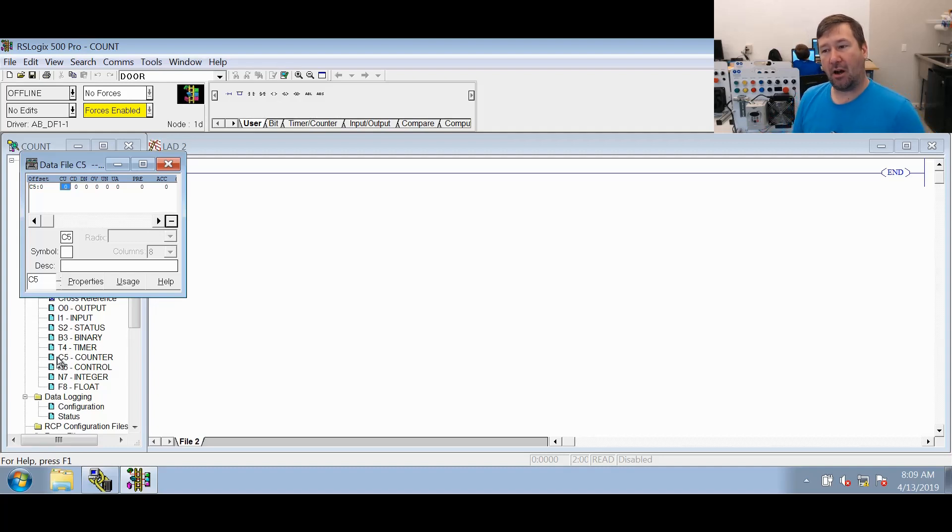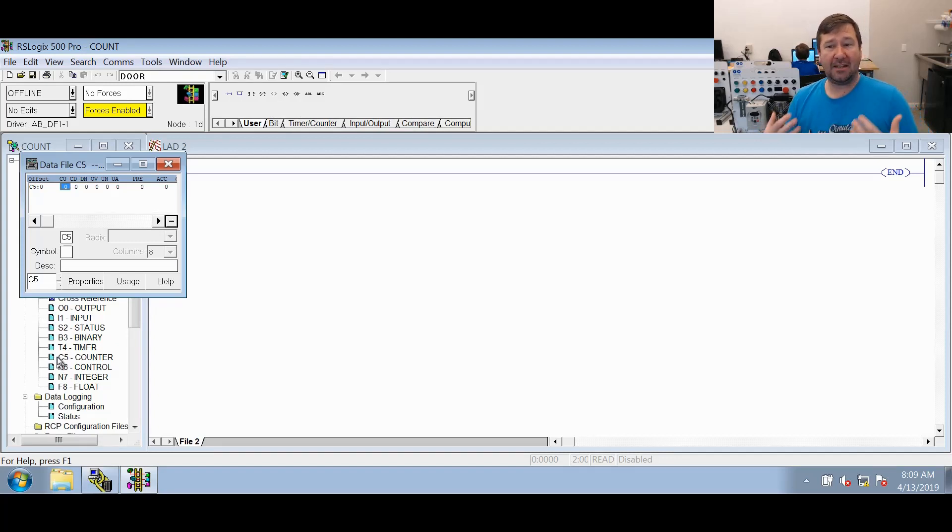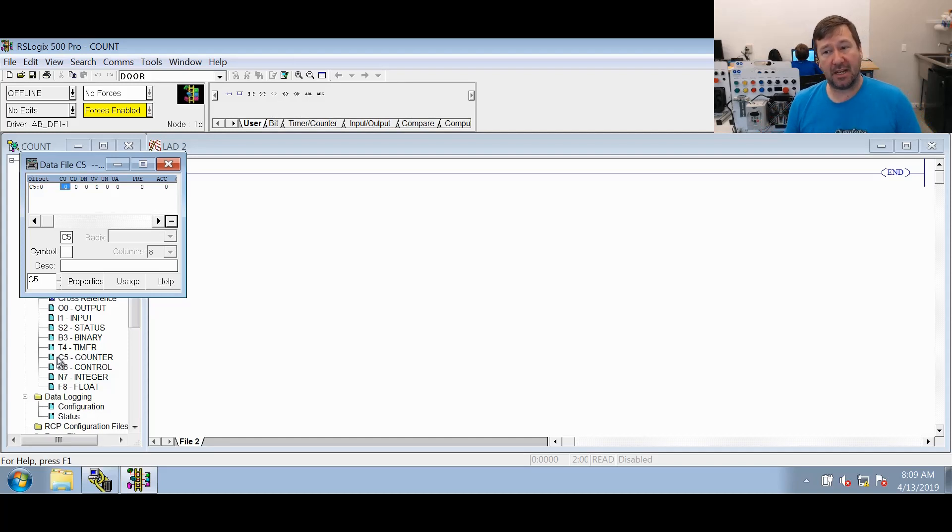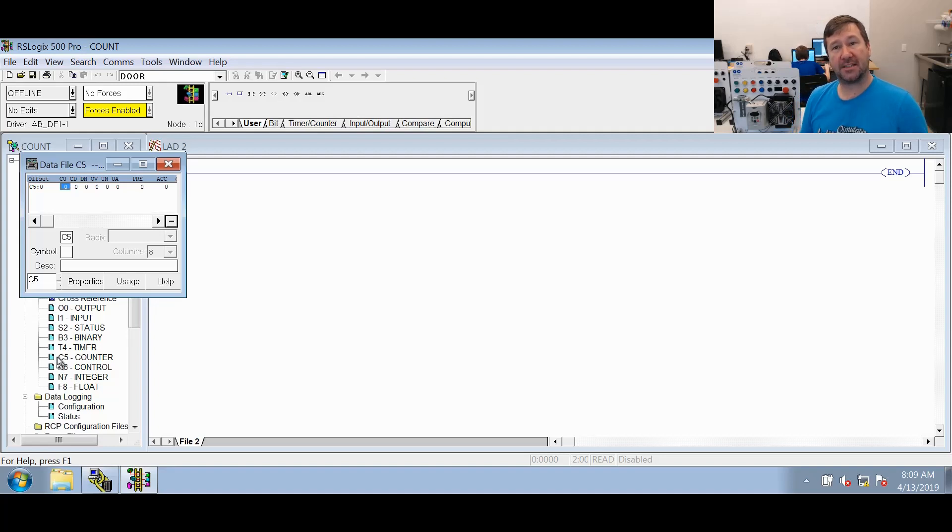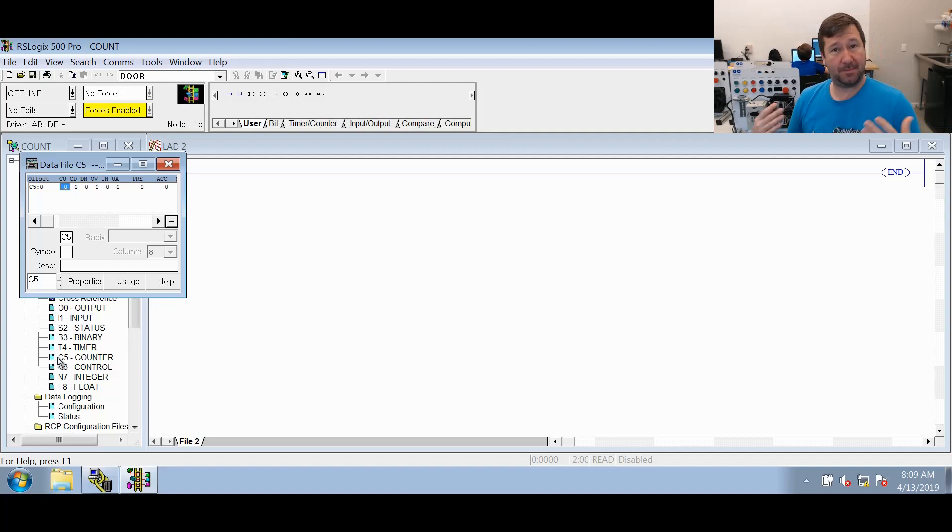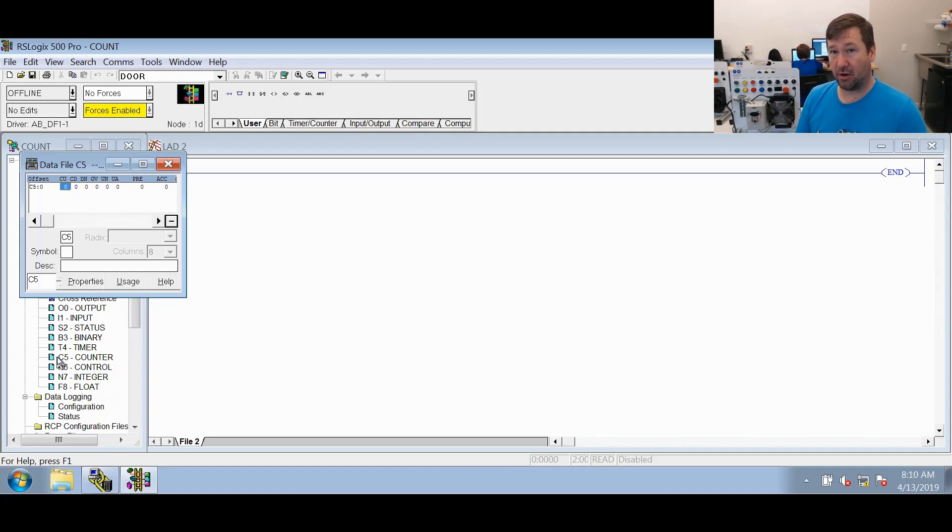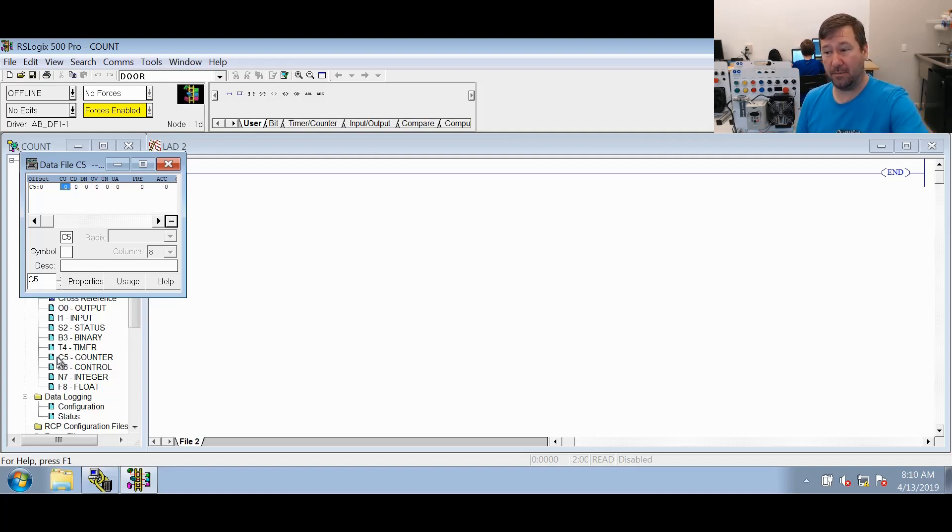We're going to put all of those in there to understand them a little better with the exception of the UA bit. The UA bit is the update accumulator and it is only used on the high speed counter of the fixed SLC controller. That's a really obsolete controller, so I'm going to say that this bit is just a legacy bit. If you see it in a program, you probably need to pay attention to it, but honestly I can't think of a time I've ever seen this bit used in a program.